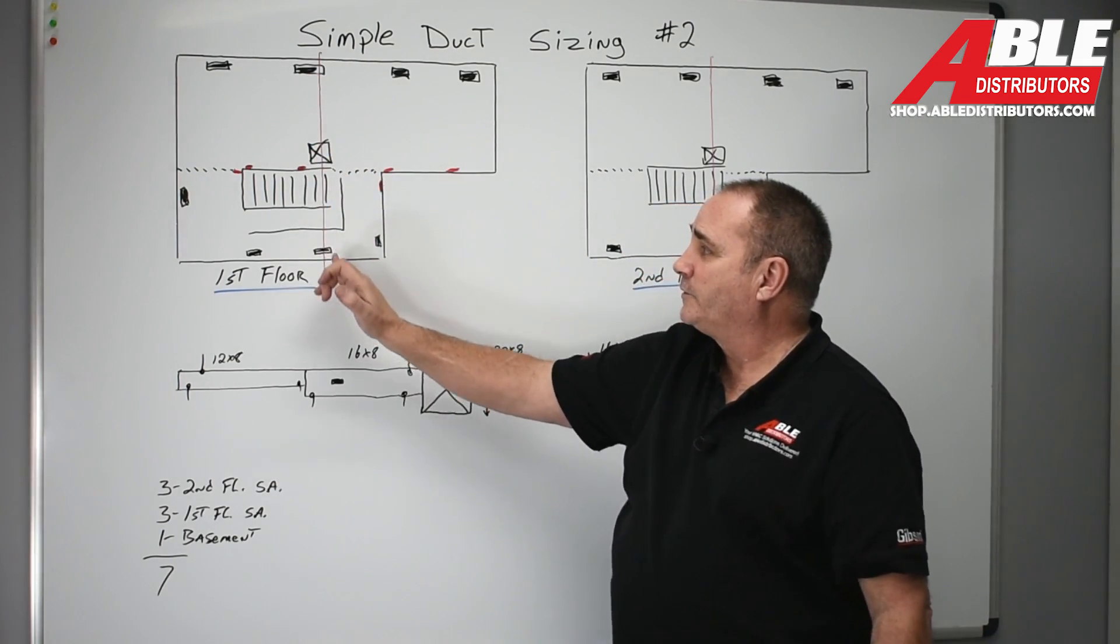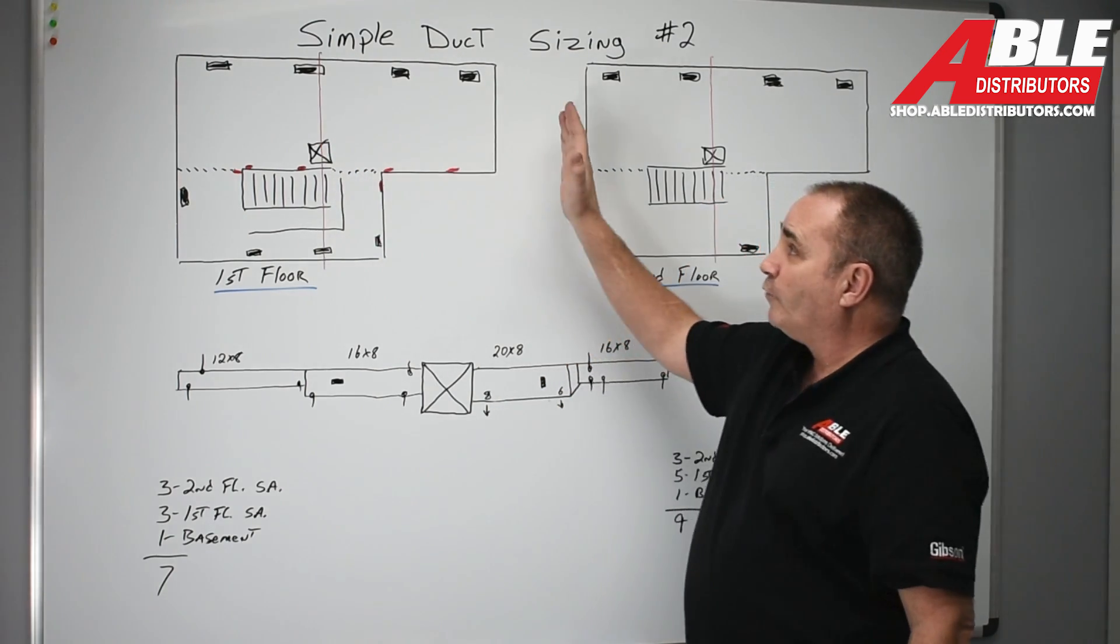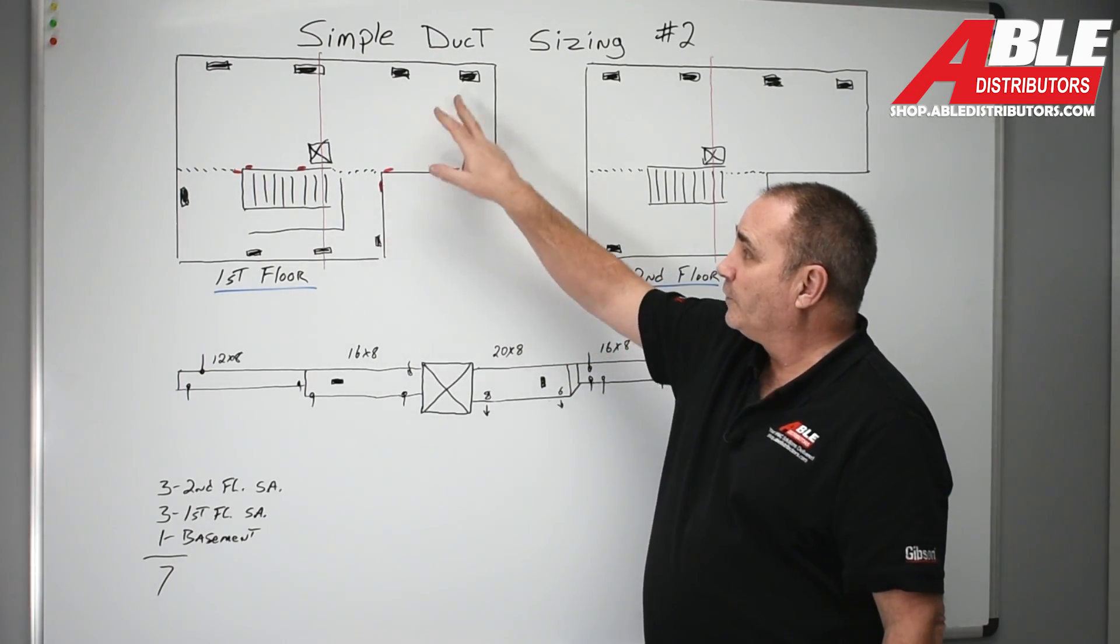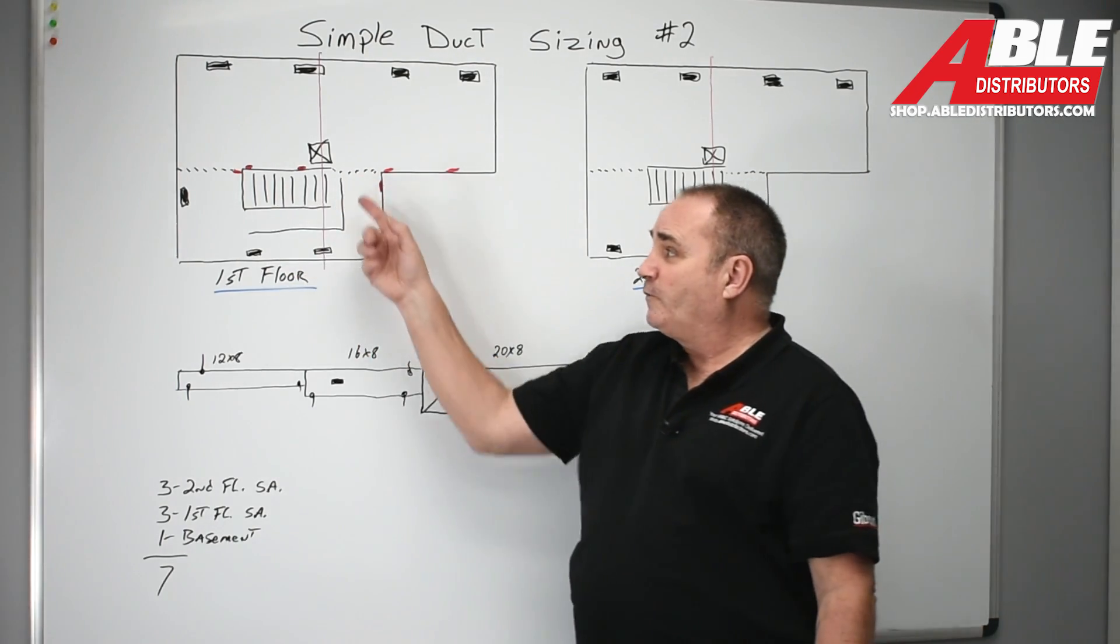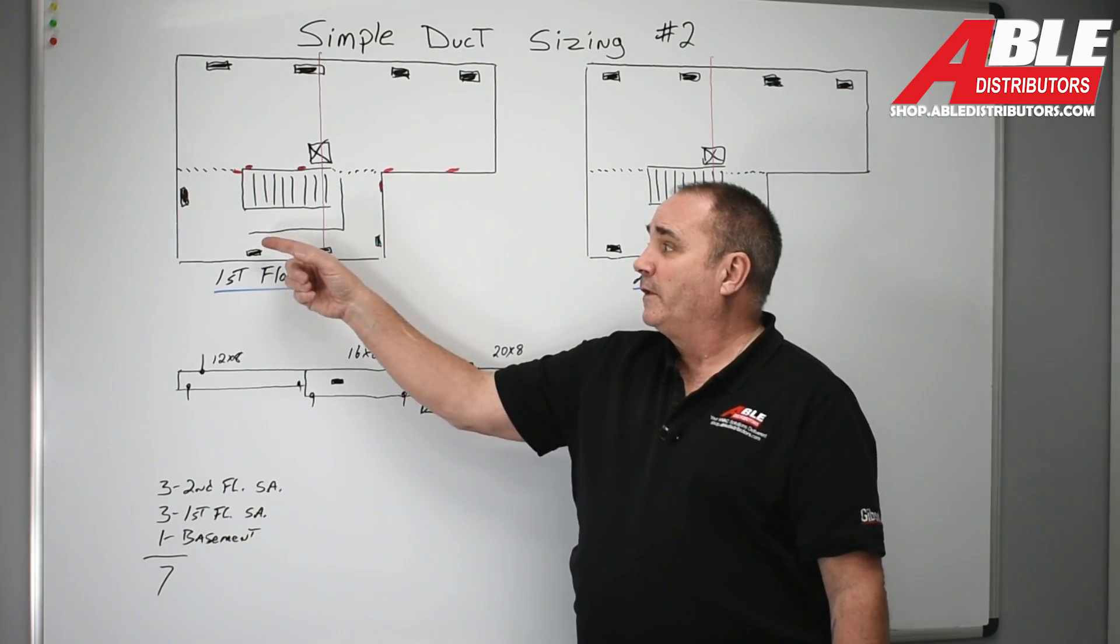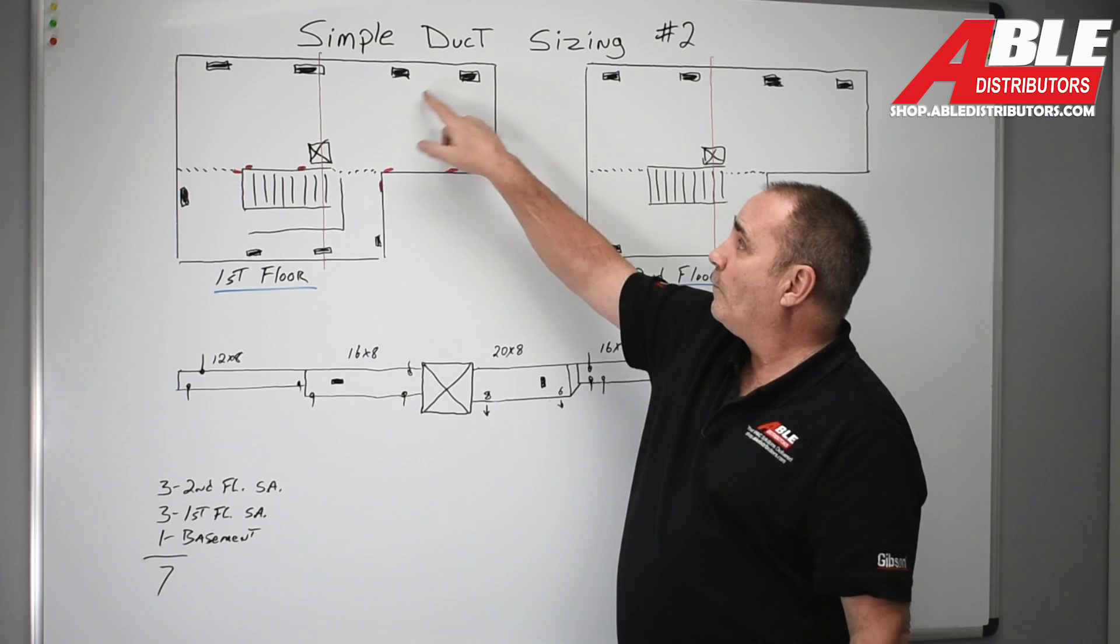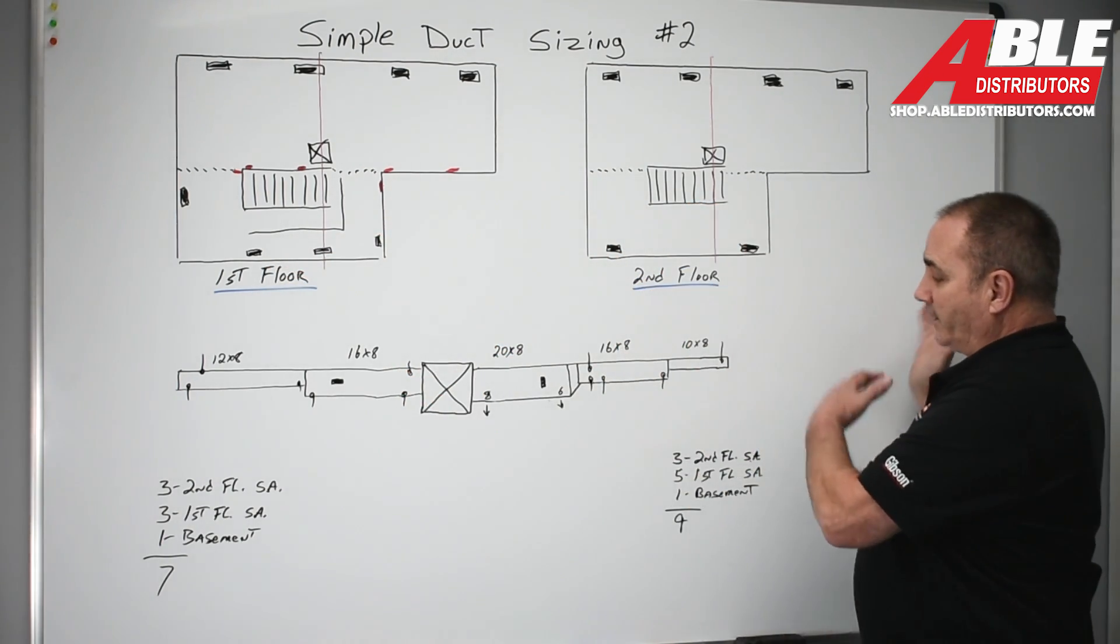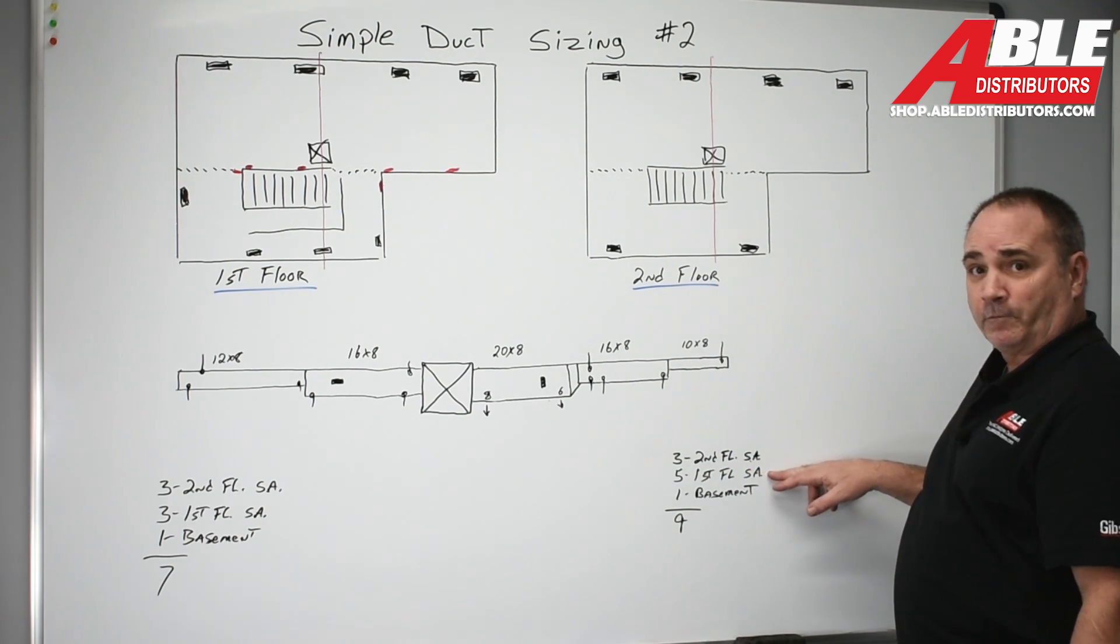So I divided the house in half right above where my furnace is going to be so I know to the right I've got one, two, three first floor supplies and I've got two on the other side of the stairwell and I have to figure out how I'm going to get there. So I just figured I'd take and jump an 8 inch to two 6 inch saddles and hit that. So I've got one, two, three, four, five. So to the right side on the first floor I've got five first floor supplies.